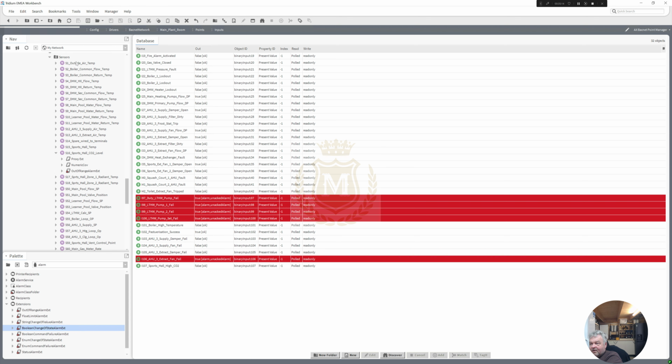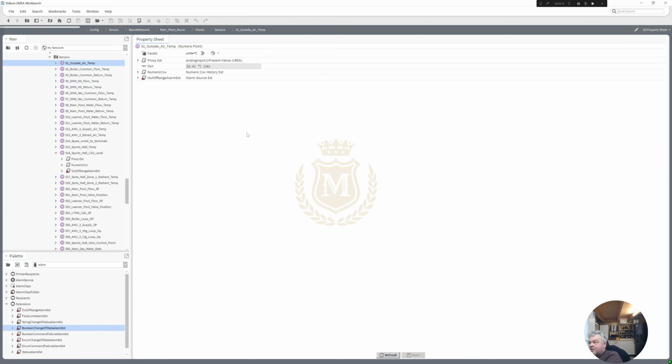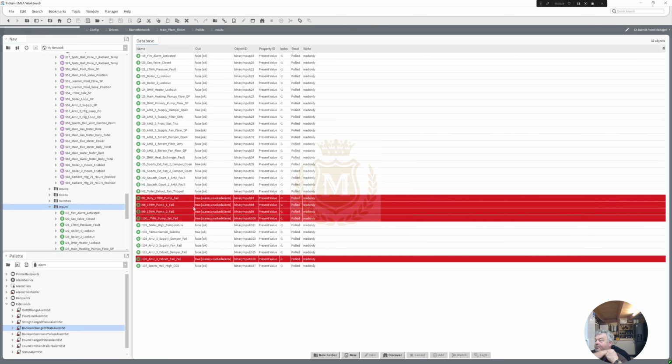We've got an outside air temperature, 22.61. Okay, so I reckon they have just turned off the pumps on the wall isolator. BMS is trying to do its stuff, and that's the reason why the duty pumps have failed, and it wants a reset sending.